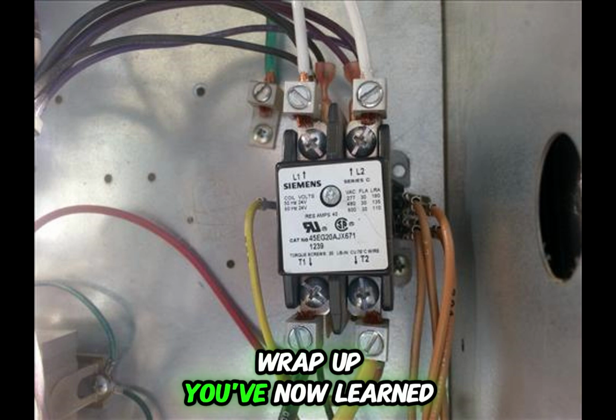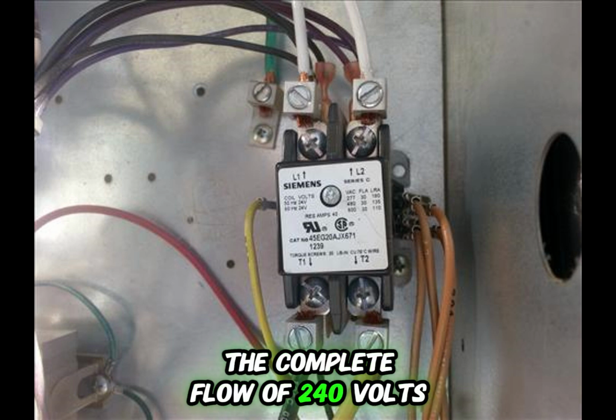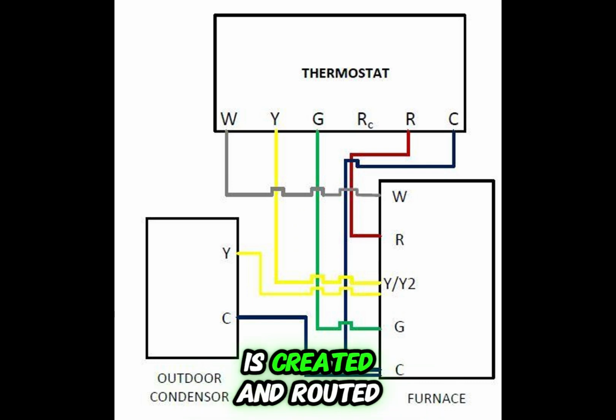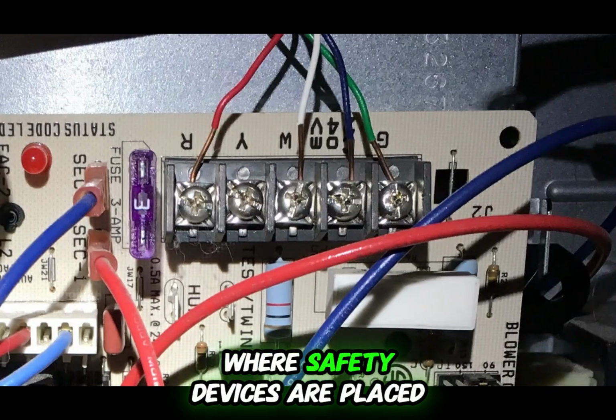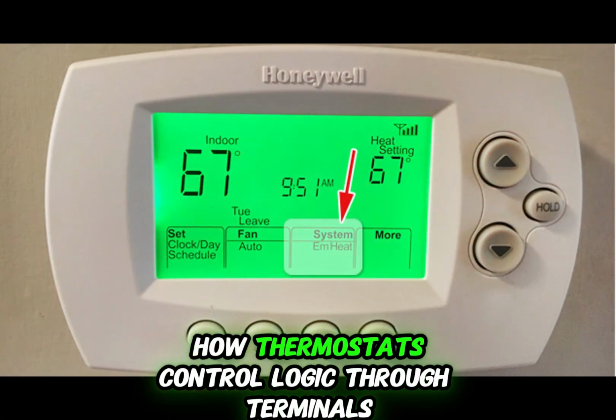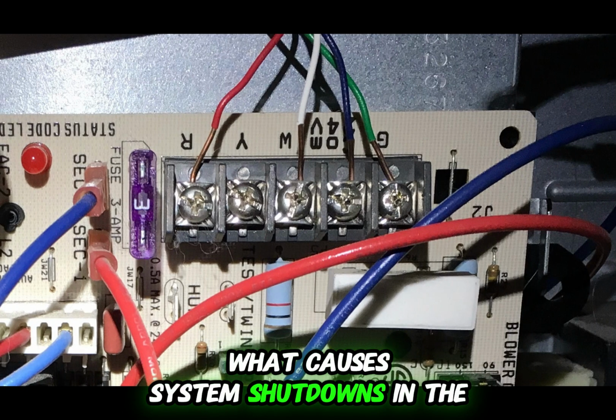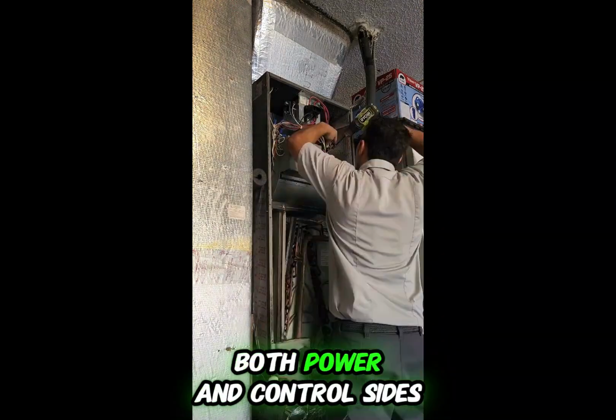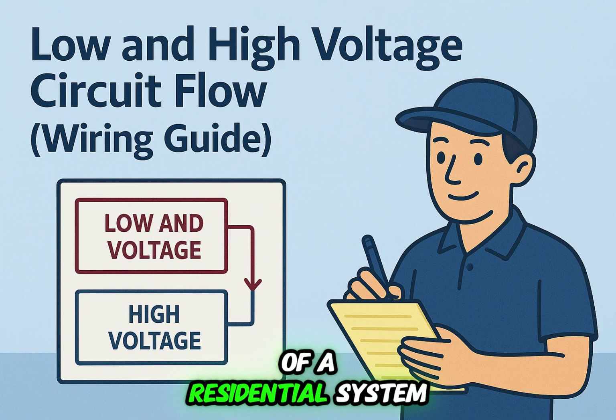Wrap up. You've now learned the complete flow of 240 volts high voltage, how 24 volts low voltage is created and routed, where safety devices are placed, how thermostats control logic through terminals, and what causes system shutdowns in the control circuit. You are now ready to trace and troubleshoot both power and control sides of a residential system.